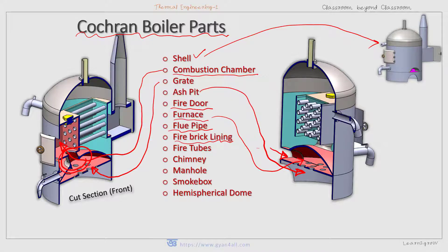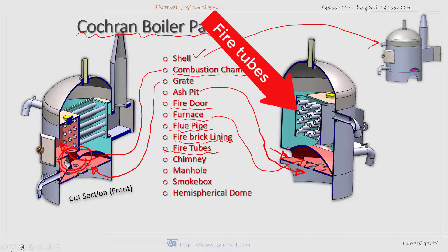Then fire brick. There is fire brick lining around the combustion chamber to minimize the leakage or loss of heat to the atmosphere. Then the fire tube — this is a very important component. These are the horizontal fire tubes connecting the combustion chamber and the smoke box. The fire tubes help in the exchange of heat from the hot flue gases to the water surrounding them. The hot flue gases from the combustion chamber travel to the smoke box through these fire tubes.